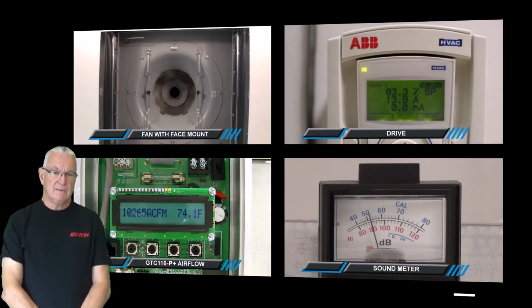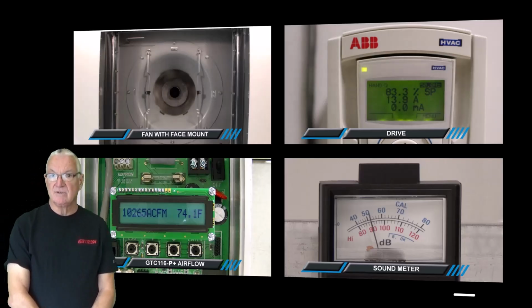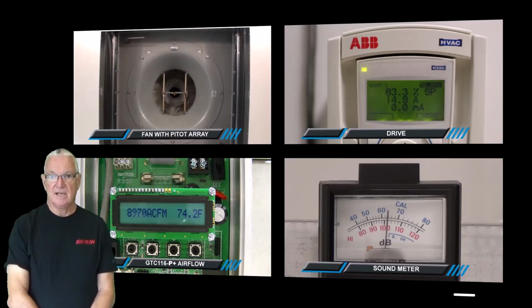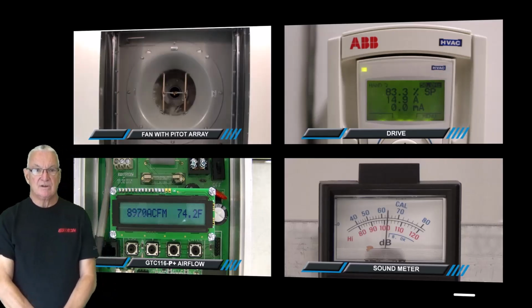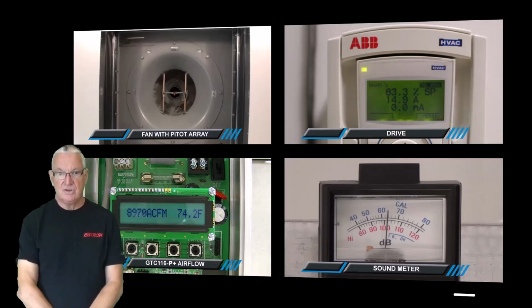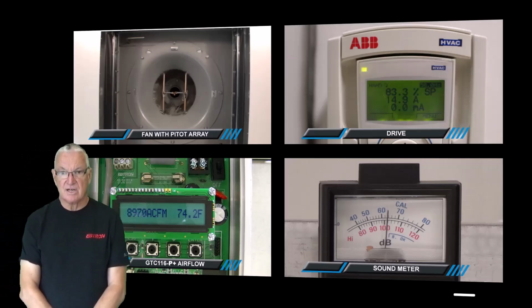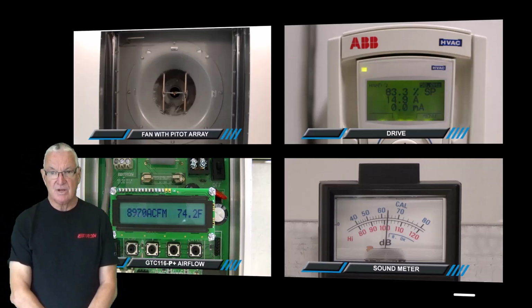We put our fan inlet unit in, and really nothing changed. Okay, the current draw is the same, the flow is the same, and the sound level is the same. Okay, if we put something like a pitot array in, and to be fair to the pitot tube, if we put what we call a throat-mounted EBTRON in, we'd have a similar situation. Current draw goes way up, the supply flow goes way down, the sound level goes way up. All right. Bottom line is we don't affect these fans.